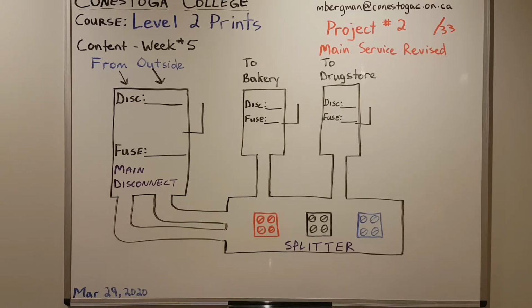It's going to be the largest of all disconnects. From there, we're going to run into a splitter, written in purple. It's just a long trough, usually maybe 3 or 4 feet long, a foot wide, and 6 to 8 inches deep, depending on the size of the splitter. So voltage and amperage would change the physical size of the splitter.